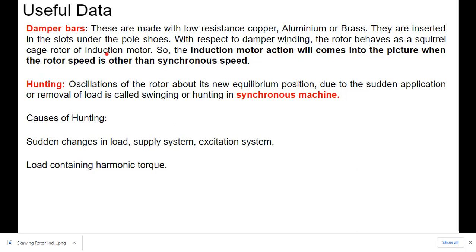And damper bars. Damper bars are used to place in synchronous machine. How damper bars look like? These are made with low resistance copper or aluminum or brass material. These are inserted in the slots under pole shoes. With respect to damper winding, the rotor behaves as a squirrel cage rotor of induction motor.